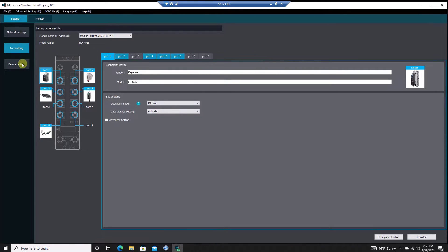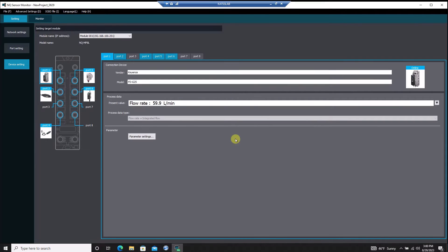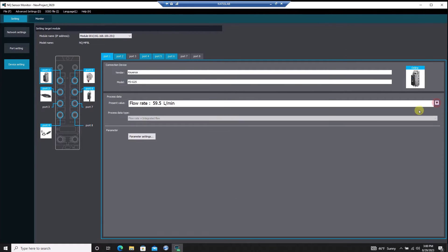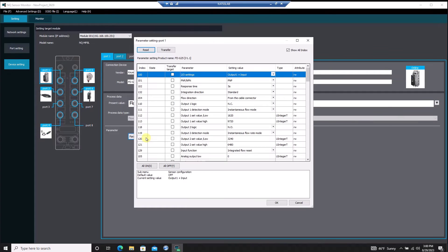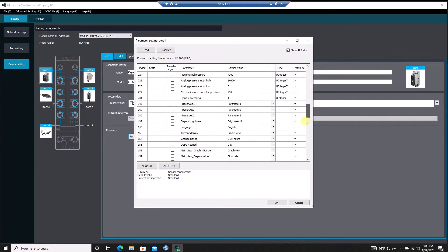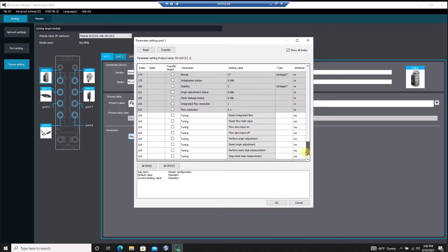In the device settings menu, we can monitor the process data that cyclically updates between the sensor and the NQ. Additionally, we can remotely configure an IO-Link device by entering the parameter settings. Here we can change settings on the device or issue commands such as tuning or initialization using the IO-Link service data.